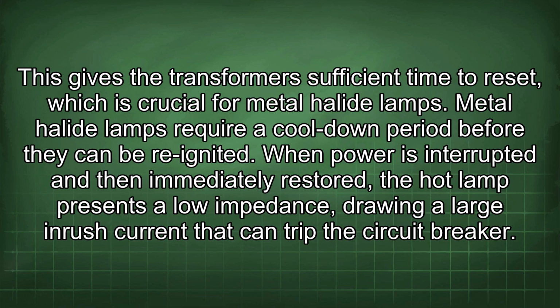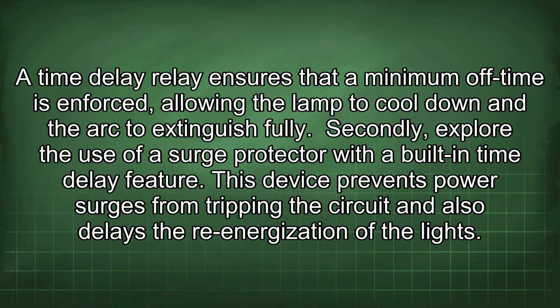When power is interrupted and then immediately restored, the hot lamp presents a low impedance, drawing a large inrush current that can trip the circuit breaker. A time delay relay ensures that a minimum off time is enforced, allowing the lamp to cool down and the arc to extinguish fully. Secondly, explore the use of a surge protector with a built-in time delay feature.